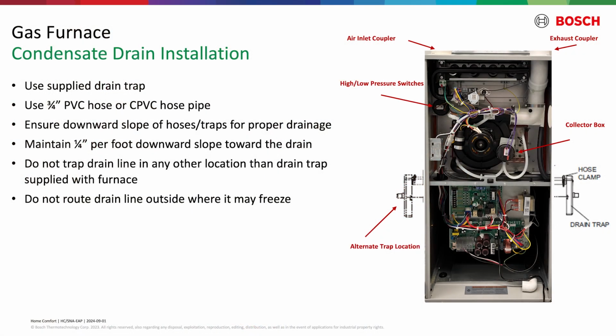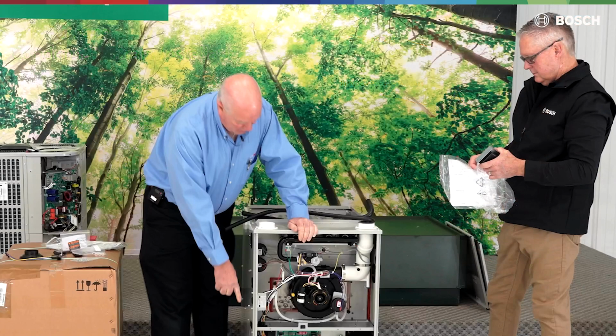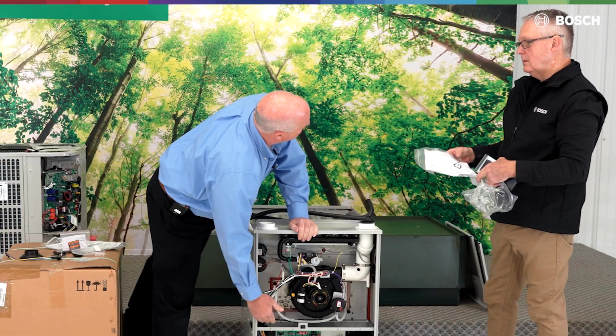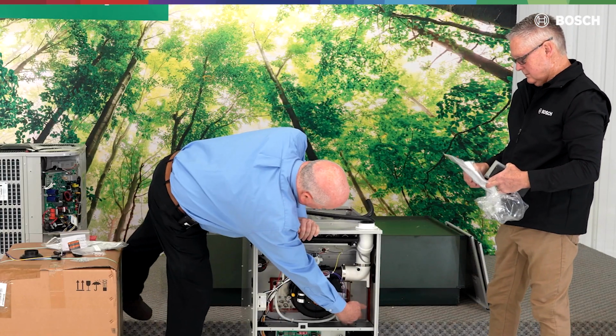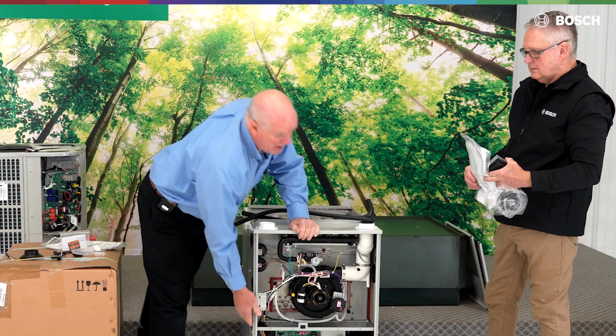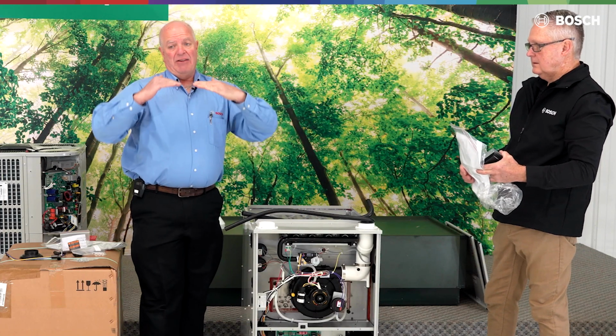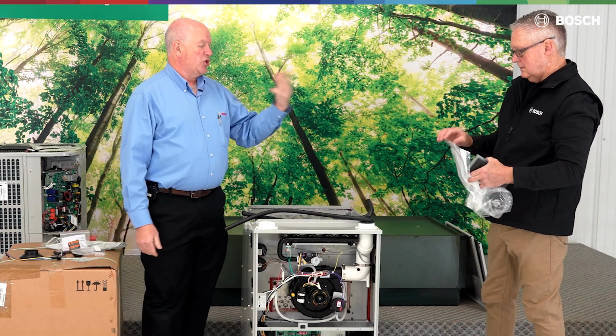The issue that's very critical is our elevation, left to right, has to be level. If it's not level, if it's leaning just a little bit one direction or the other, the water will not run out of that into our trap, and it'll be plugged with this hose. We have 5/8 of an inch of fall coming from here to the connections over here. 5/8 is not a lot to have a little deviation on our slope.